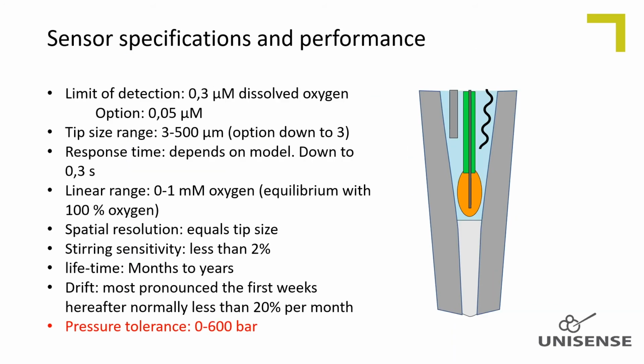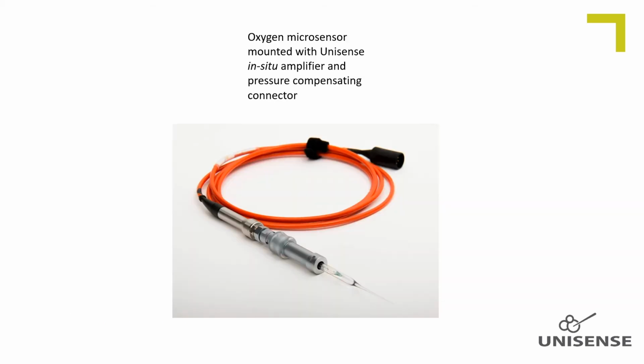Oxygen sensors stand up to 5 times atmospheric pressure without being pressure compensated. However, like other Unisense microsensors and electrodes, we can pressure compensate the inner parts of the sensor so they can withstand full oceanic pressure. When pressure compensated, they are tested to be able to withstand 600 bars.